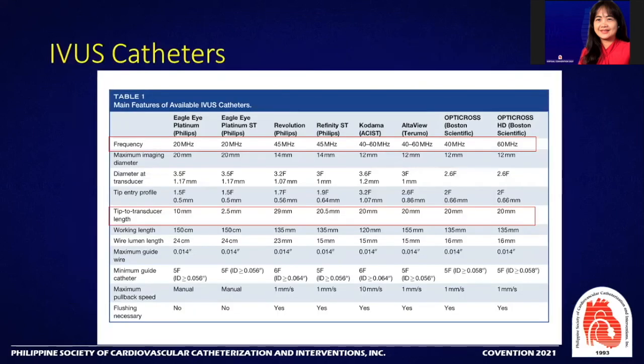This table is a table of the different Ivus catheters available in the market. Notice they have different ultrasound frequencies, which is significant because with a higher frequency, you would have good resolution of the image. However, the field of vision is shallower. The lower frequency, on the other hand, will give you a deeper field of vision, sacrificing good resolution.